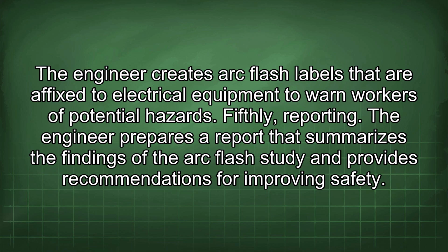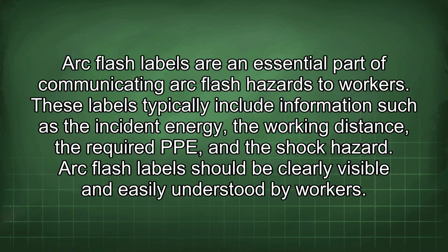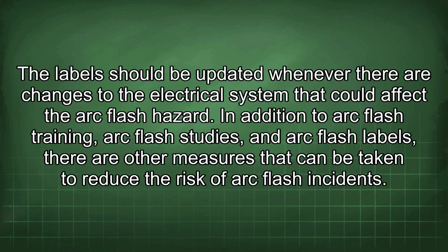Arc flash labels are an essential part of communicating arc flash hazards to workers. These labels typically include information such as the incident energy, the working distance, the required PPE, and the shock hazard. Arc flash labels should be clearly visible and easily understood by workers. The label should be updated whenever there are changes to the electrical system that could affect the arc flash hazard.